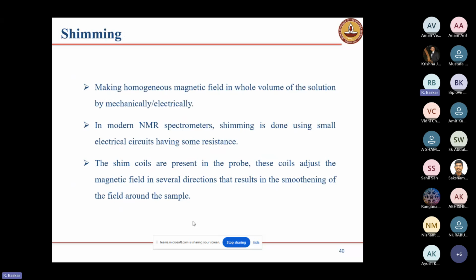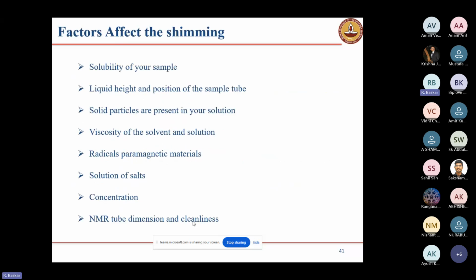Once shimming is done... sorry, these are the factors that affect the shimming. First one is the solubility. If your sample has poor solubility and some solid particles are there, it will affect the shimming. Liquid height: you have to take the proper height of your solution. If you are not taking the proper volume of the solution, it will affect the shimming. If solid particles are present in your sample, that will also affect the shimming.